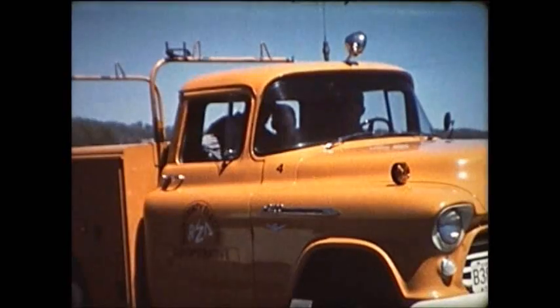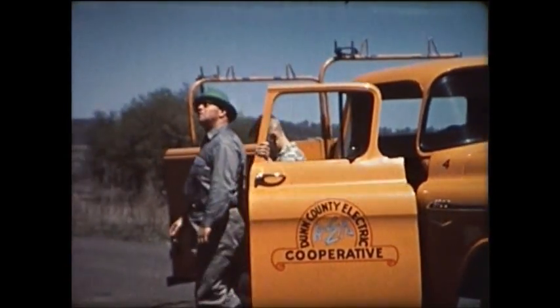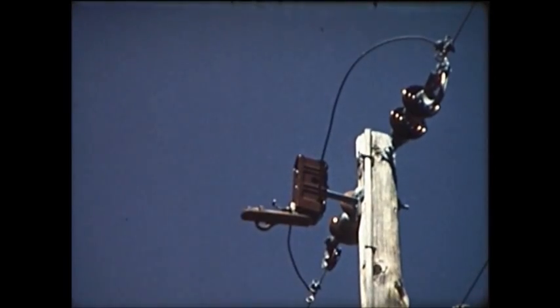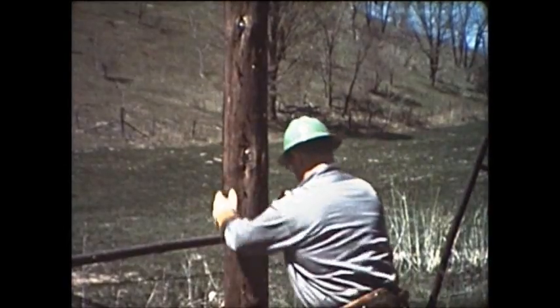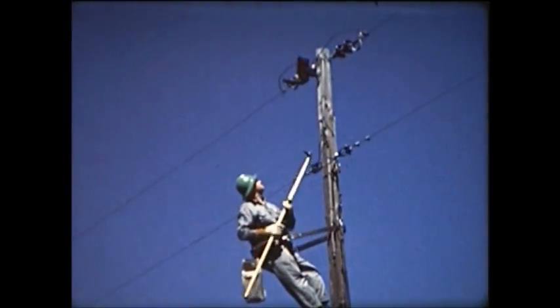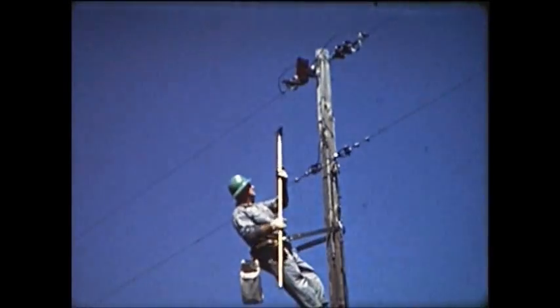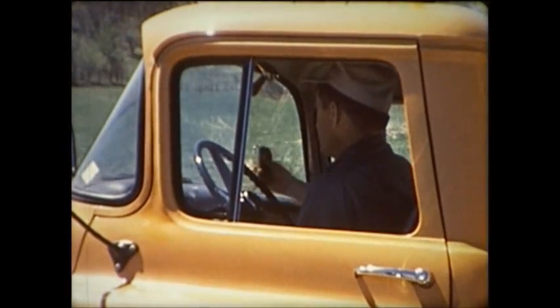The first step is to check the fuses on the circuit that is out. Bill's dad knows the location of these fuses by heart. This fuse has blown. He may find that all he has to do is replace it and service is restored. But the new fuse blows instantly, indicating that there's a short circuit somewhere on this section of the line.